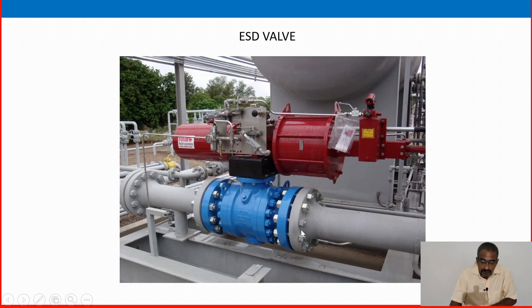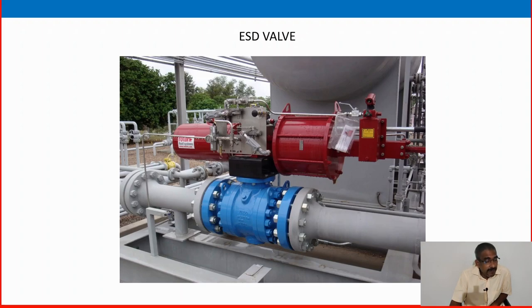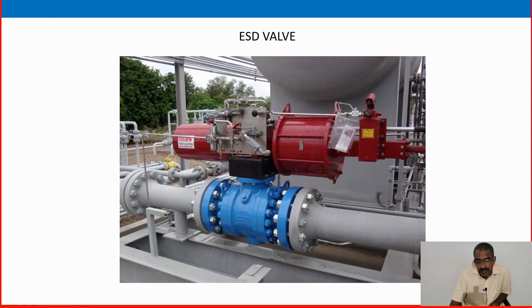Hope you have seen the ESD valve in your plant area. Most of the time, an ESD valve is made as a ball valve. We will take a specific video on valves — various types, their specifications, peculiarities, characteristics, advantages, and disadvantages. Briefly, a ball valve is used for ESD valves because of its fast, quick-closing and slow-opening property. This is an ESD valve, where you can see the pneumatic air system with regulators.